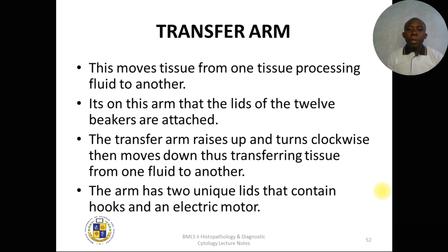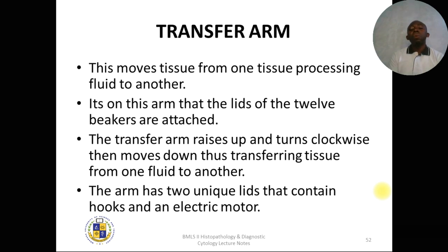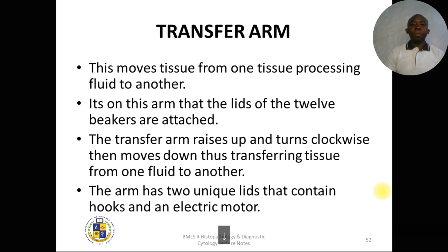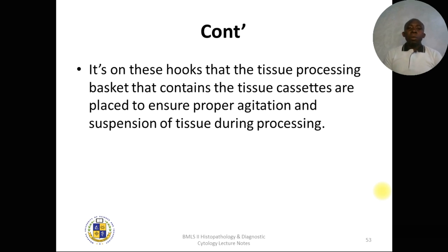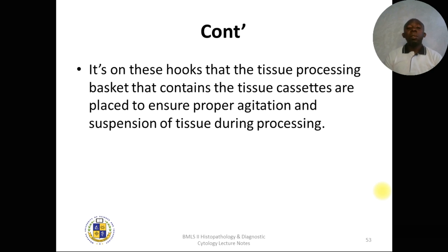The transfer arm rises up, turns clockwise, and moves down — transferring the tissue from one fluid to another. The arm has two unique lids with hooks and an electric motor that drives movement and rotation between positions. The tissue processing baskets containing cassettes are placed on these hooks to ensure proper suspension of the tissue during processing, which is essential for good fixation and dehydration results.